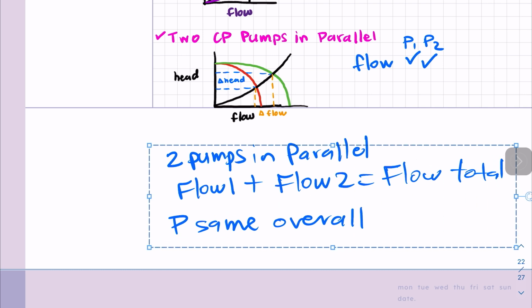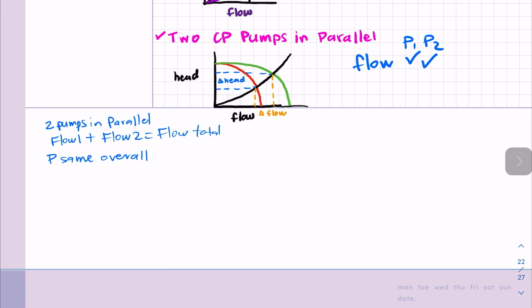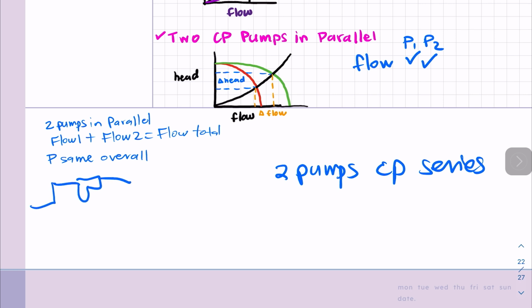But when we have 2 pumps in series, so when we have 2 centrifugal pumps in series, they are installed so that the discharge of one pump is connected to the suction of another pump, right? So, okay, let me just draw this one. It's always good to draw. This is parallel. This is series.